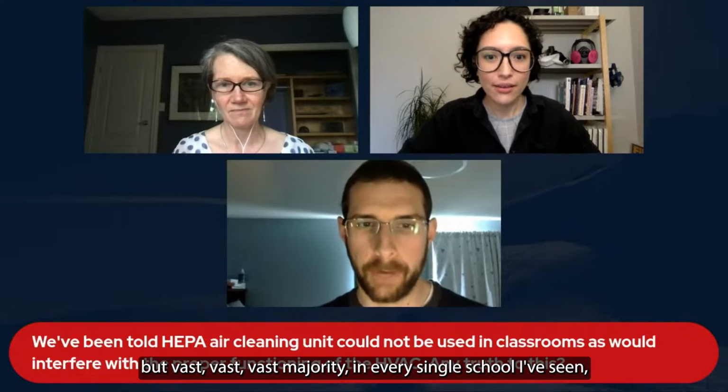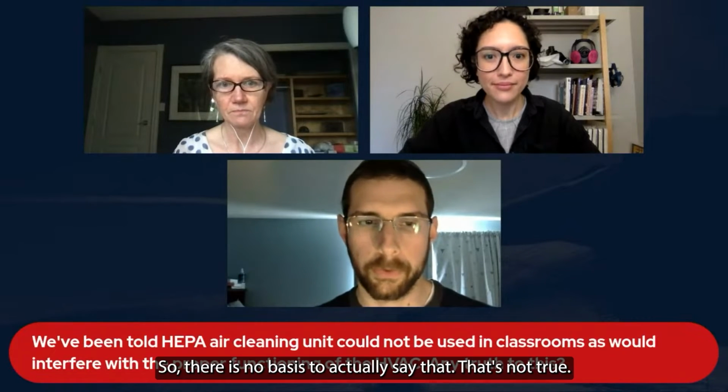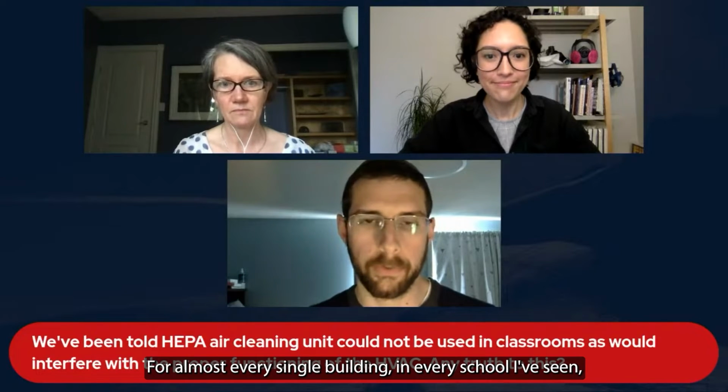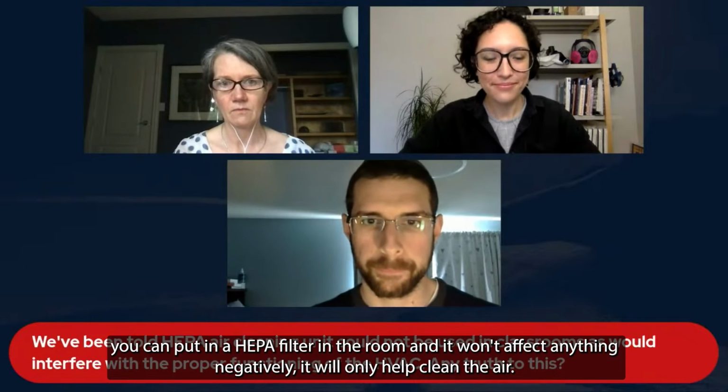But the vast majority, in every single school I've seen, it uses what's called dilution ventilation, where it just mixes the air in the room. So there is no basis to actually say that. That's not true. For almost every single building in every school I've seen, you can put in a HEPA filter in the room and it won't affect anything negatively. It will only help clean the air.